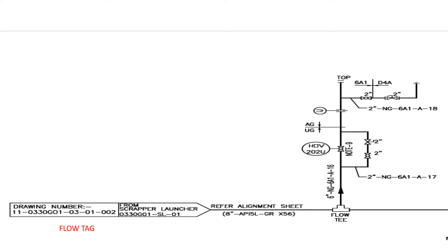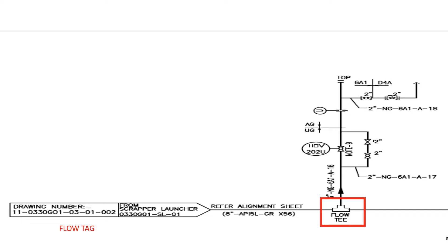The main line divides into two streams through a T joint. As flow T is mentioned here, it is understood that a special type of fitting called flow T is used in this pipeline. Any special type of fittings used will be clearly mentioned like this in a P&ID.